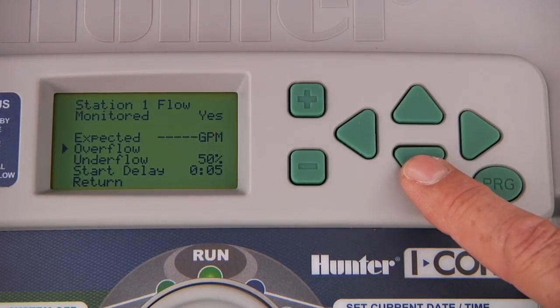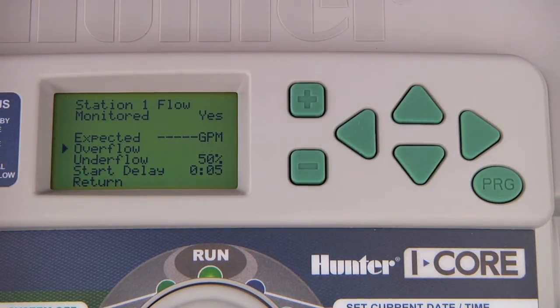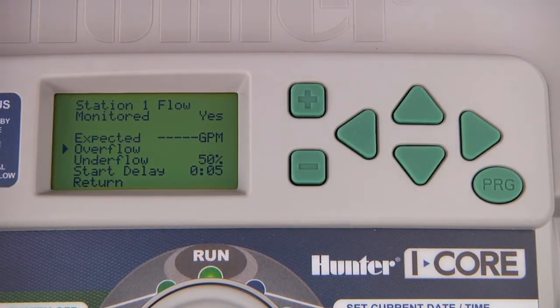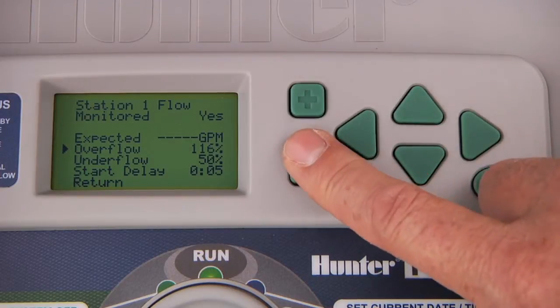The next option is overflow, and this is the limit at which the controller reacts when overflow conditions are detected. The default is 115%, which means that if the controller records flow conditions that are 15% over the expected flow, it will send an overflow alarm and shut down irrigation for that station. You can change this number from 110 to 300%.